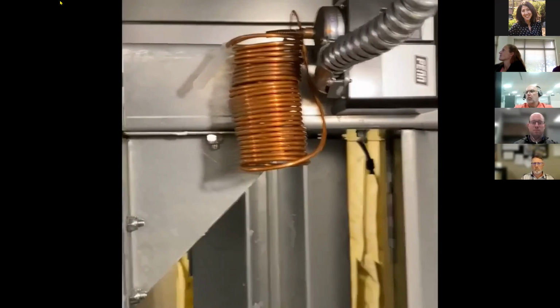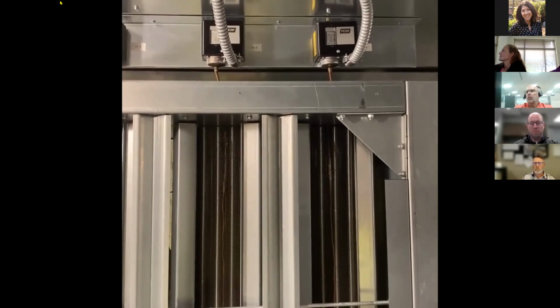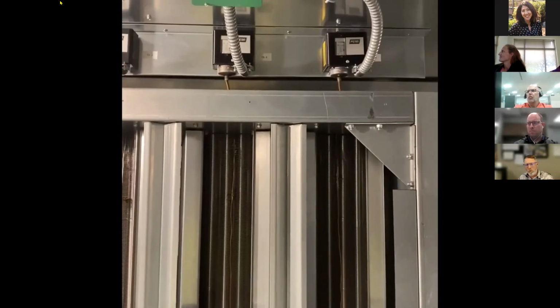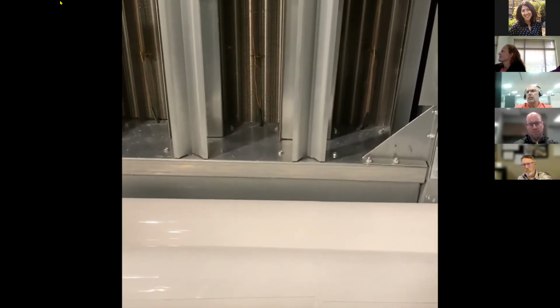So this seems to be a problematic installation. You might recall an earlier installation where the freezestats were rotated 90 degrees and all sorts of other chaos. But now this is a textbook installation with the freezestat up on top, line running vertically down the element of the coil, and the contractors have already covered up the remaining freezestat element at the bottom.